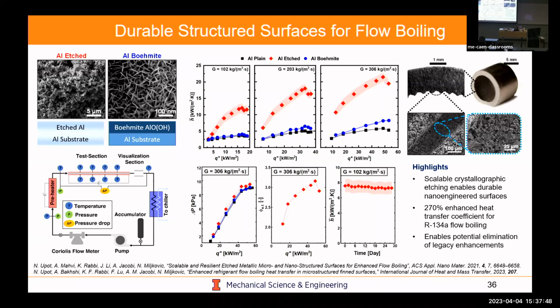So one piece of work we've done is looking at refrigerant flow boiling. This is the heat transfer coefficient for these etched surfaces compared to a plain or a boehmite surface, as a function of heat flux for three different mass fluxes. What you'll see is about a 250 to 300% increase in your heat transfer coefficient just by pre-processing your tube with this etch chemistry — HCl in this case.